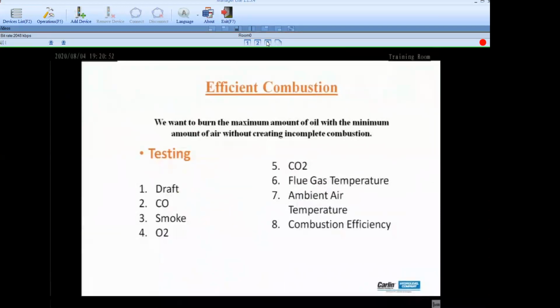Testing. Many guys understand how to do a combustion test. They have an analyzer, they plug it in, it's digital, it gives them some kind of readings. The only thing they need to do is possibly select the fuel type, and then they expect some type of results to be given back to them from that analyzer. And they look at these numbers and say, well, okay, my CO2 is X and my stack temperature is Y. Those are good. Or they say, well, they're not good, but have no clue and no understanding of why they're not good or what steps are necessary to affect those changes.